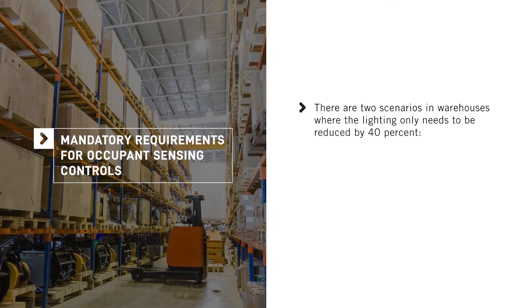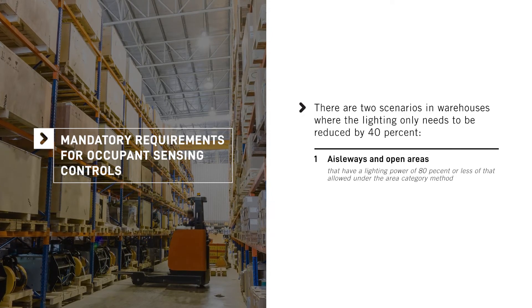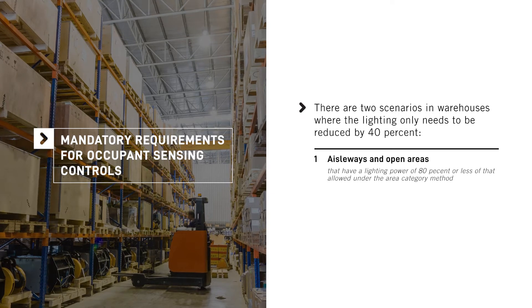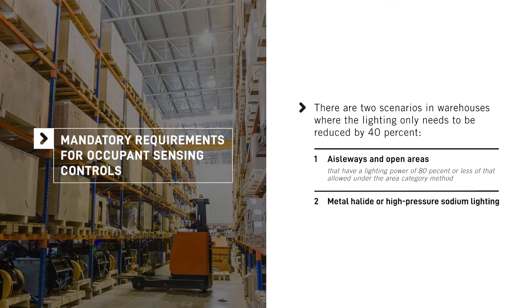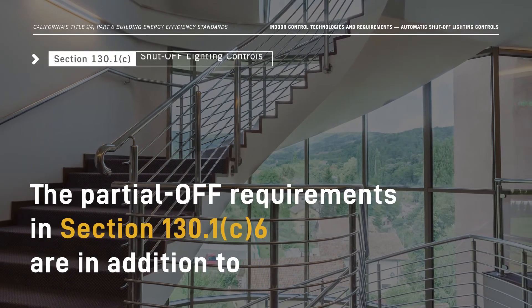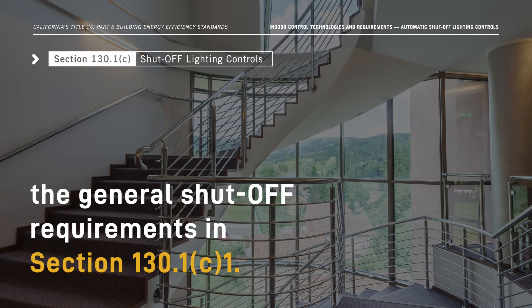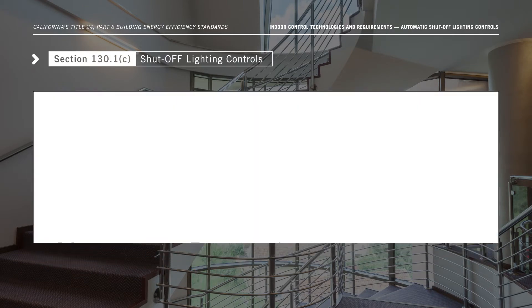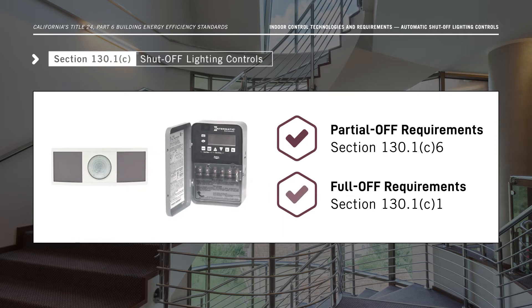There are two scenarios in warehouses where lighting only needs to be reduced by 40 percent: when aisleways and open areas have a lighting power of 80 percent or less of that allowed under the area category method, and when metal halide or high pressure sodium lighting is installed. It's important to note that the partial-off requirements in Section 130.1c6 are in addition to the general shutoff requirements in Section 130.1c1. A partial-off occupancy sensor satisfies Section 130.1c6; however, a full-off occupancy sensor or time switch is required to satisfy Section 130.1c1, which requires automatic shutoff when the space is normally unoccupied.